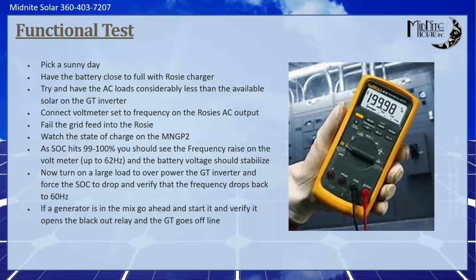So this is I think my final slide, and this is my functional test. There's a couple of caveats to this. The battery needs to be close to full, and you really need a pretty sunny day. So what you're going to do is roll to the site on a pretty sunny day. You're going to get the battery up to 90% state of charge or whatever, get it close to full, and you're going to make sure the loads are less than what the grid tie inverter can produce. Ideally, you would have the loads just powered from the grid.